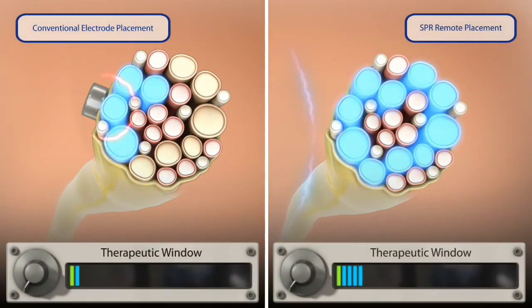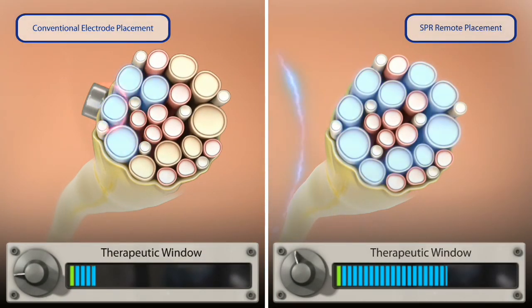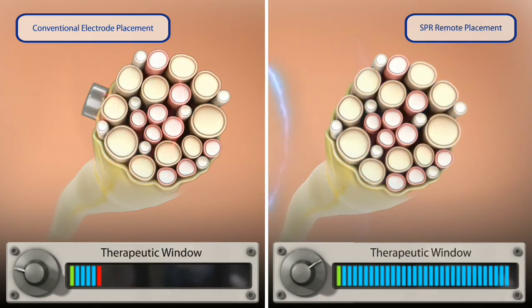The more intimate placement of electrodes relative to the nerve increases the potential to affect unintended fibers resulting in a significantly reduced therapeutic window. The ability to deliver stimulation remote to the nerve enables ease of implantation and the preferential activation of only the desired fibers.